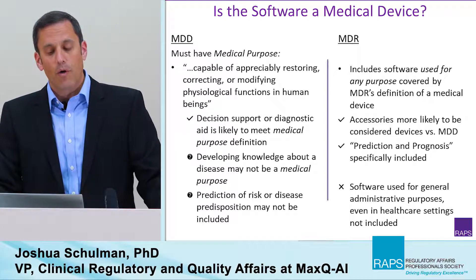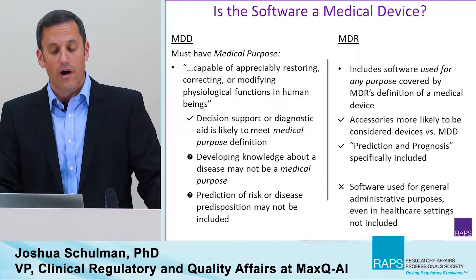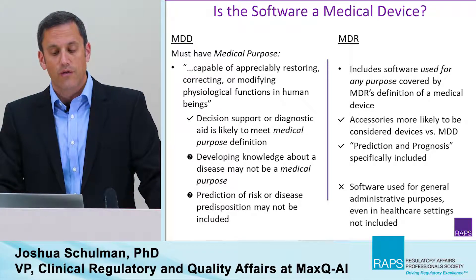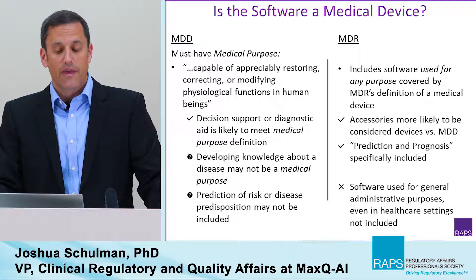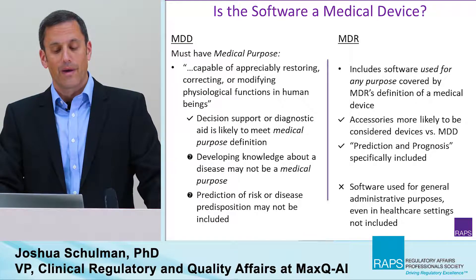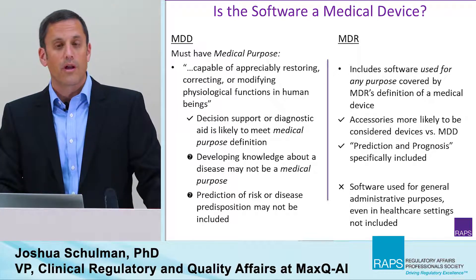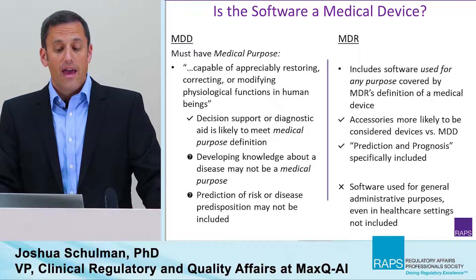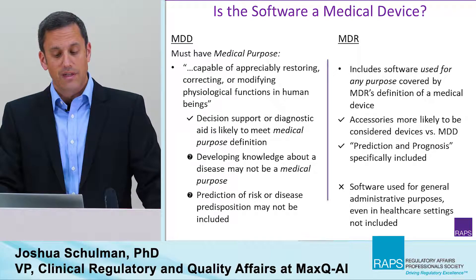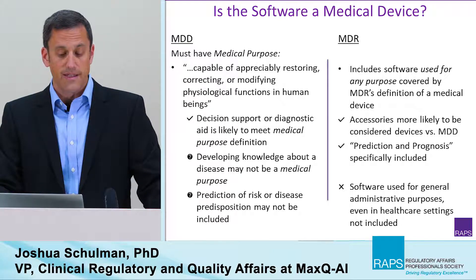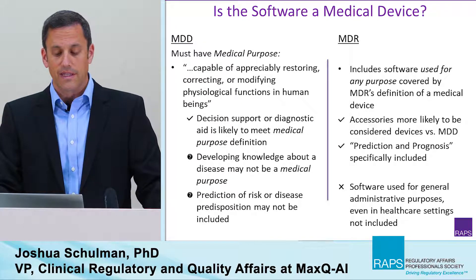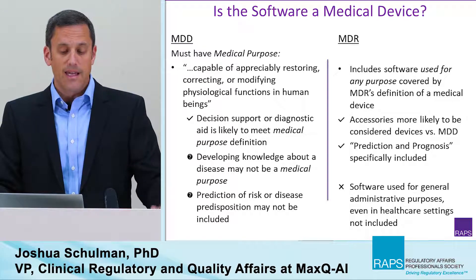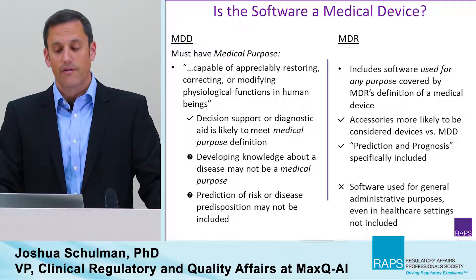This is changing somewhat as we transition to the MDR. The MDR is specific about including software used for any purpose that's covered by MDR's definition of a medical device. In addition, accessories are more likely to be considered devices compared to in the MDD. Also, prediction and prognosis is specifically included in the MDR criteria for medical devices. At the same time, software that's used for general administrative purposes, even in healthcare settings, is exempted from definition as a medical device within the MDR.